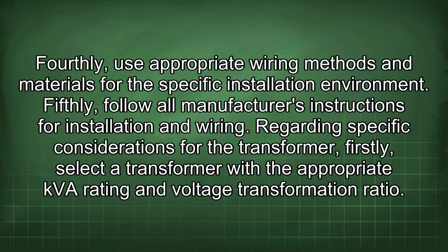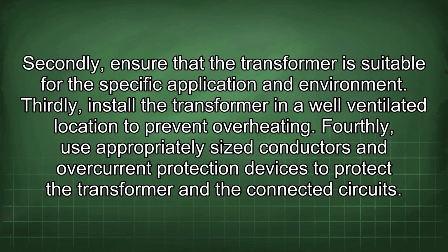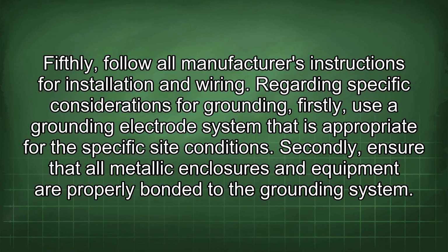Regarding specific considerations for the transformer, firstly, select a transformer with the appropriate kVA rating and voltage transformation ratio. Secondly, ensure that the transformer is suitable for the specific application and environment. Thirdly, install the transformer in a well-ventilated location to prevent overheating. Fourthly, use appropriately sized conductors and overcurrent protection devices to protect the transformer and the connected circuits. Fifthly, follow all manufacturer's instructions for installation and wiring.